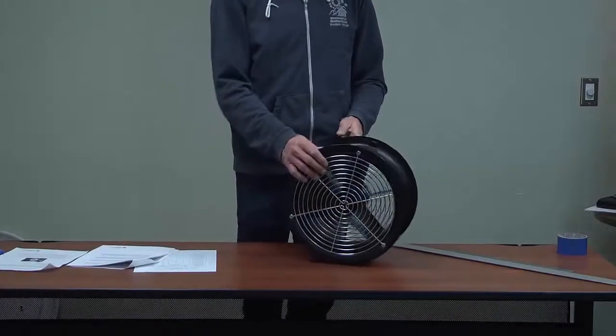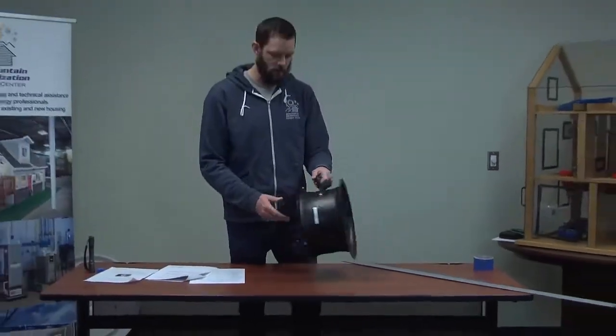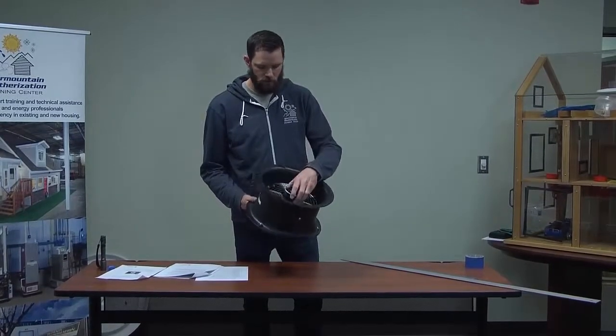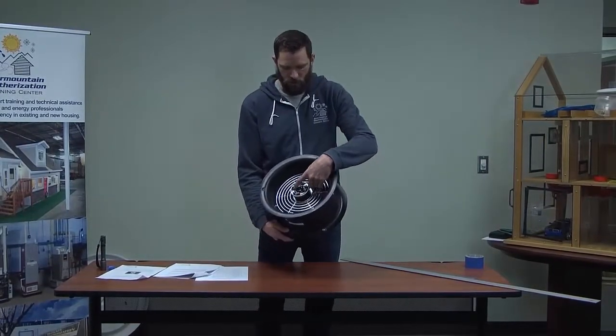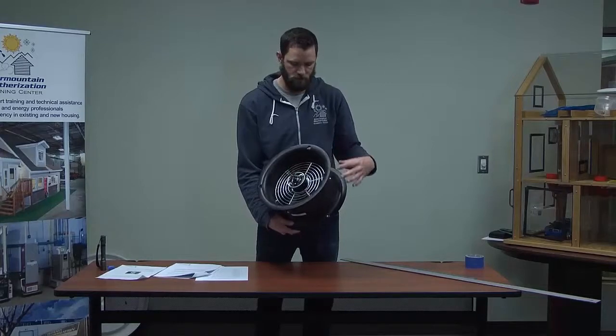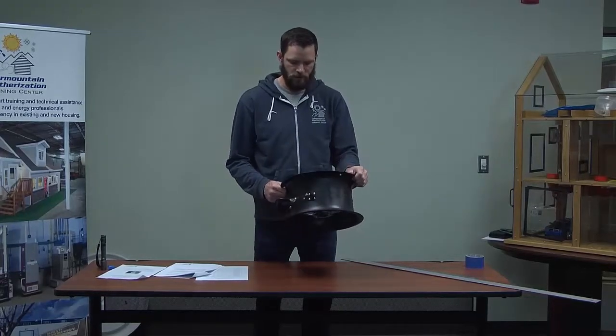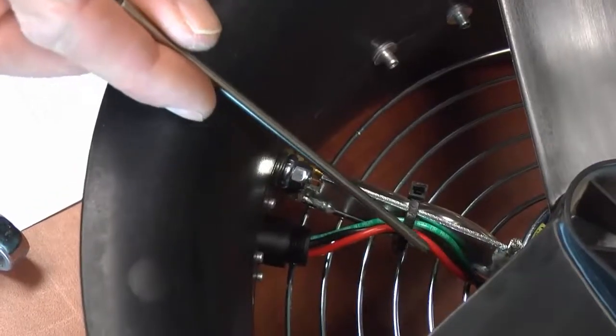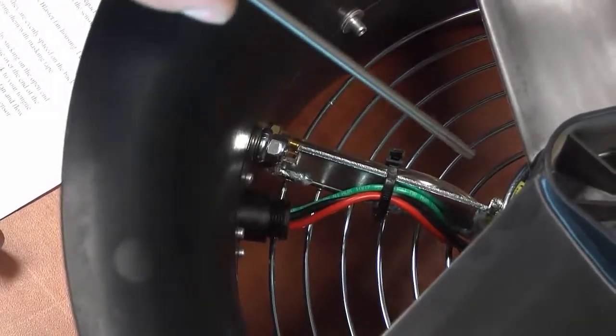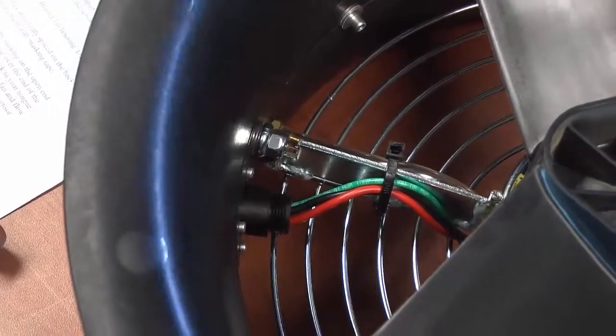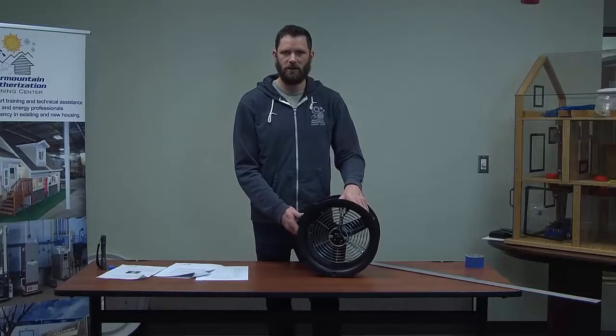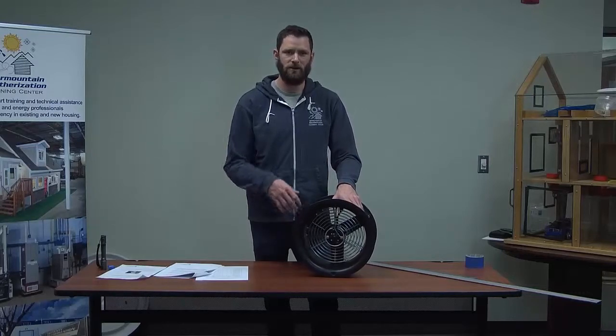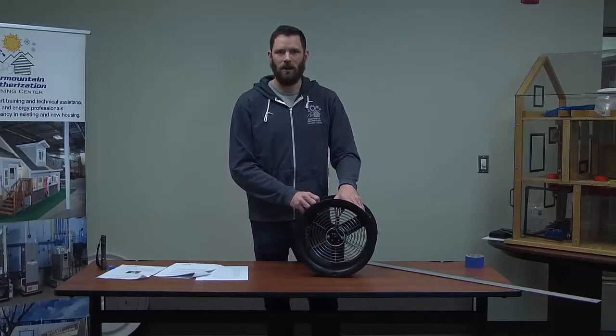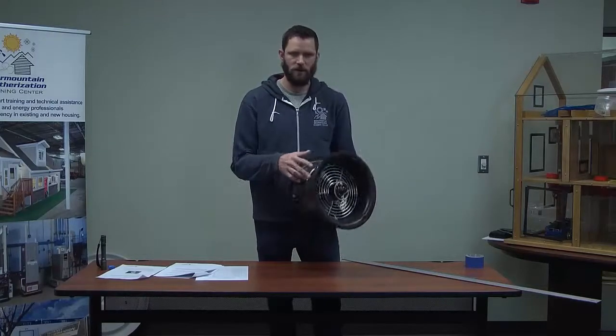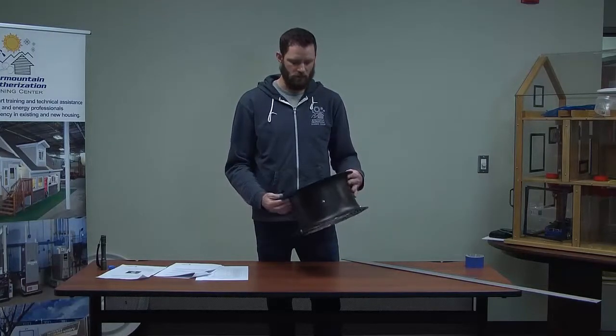Some of the other general maintenance stuff, you want to check the motor and make sure all the cooling holes in the motor are not clogged. You're also looking at the wiring, tubing, and the housing. You want to make sure it's not cracked. You're just doing a good visual inspection. If it looks like your Duct Blaster's been dropped or damaged, and the housing and stuff is cracked, you may want to send it in or get further guidance from the Energy Conservatory.